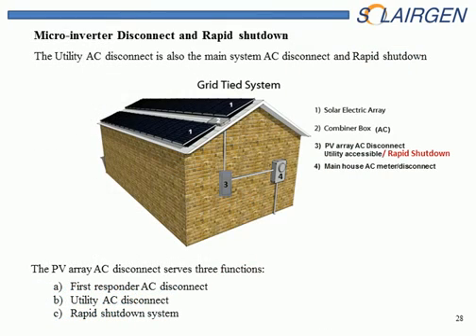Here we have the standard installation of a microinverter and the rapid shutdown. What we have is PV modules on this roof with microinverters behind them. We have a combiner box up on the roof that feeds down to the AC disconnect. Disconnecting this or pulling the meter shuts down everything to the module level up here.